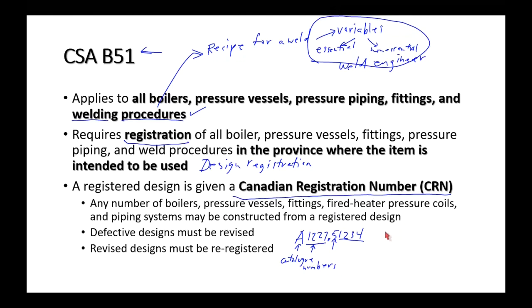You cannot install or use a boiler, pressure vessel, or pressure piping system unless it is a registered design. If you bought a used boiler in the USA and brought it to Canada without a CRN, you could store it but couldn't use it as a boiler. You'd have to contact the jurisdiction, declare it a non-CRN vessel, and go through the registration process.